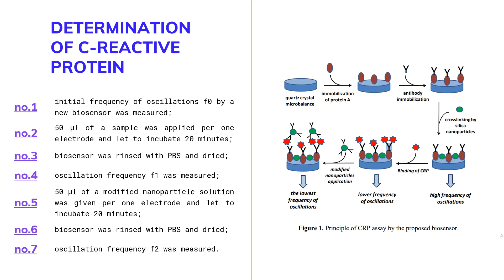The determination of C-reactive protein follows a series of steps. Looking at the given steps, it can be seen that the focus in this study is on the oscillation frequencies. Oscillations in frequency occur when the particles inside the sample, especially the CRP, start binding with each other. The biosensor executed for CRP assay helped determine both F1 and F2 using the samples prepared and calibration scale. The achieved limit of detection is also lower than demanded for clinical praxis, which makes the piezoelectric immunosensor a promising diagnostic tool.